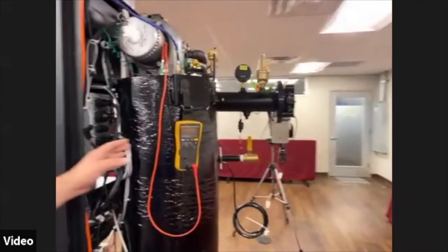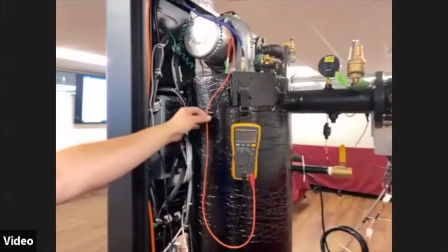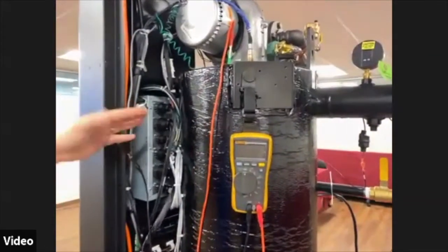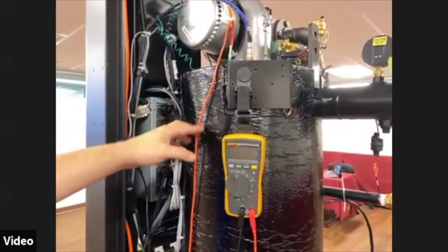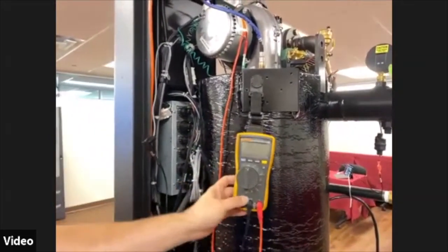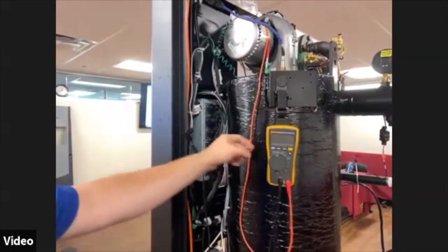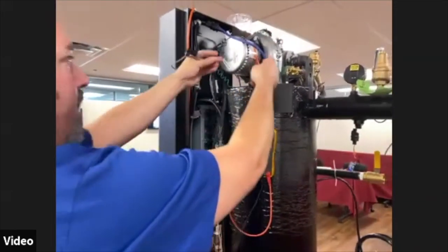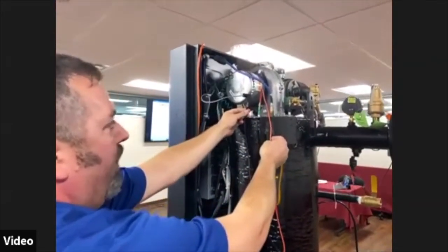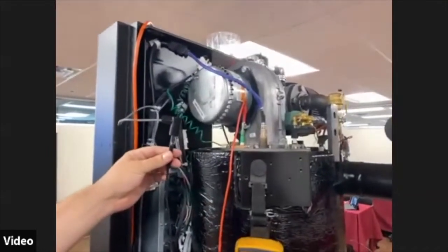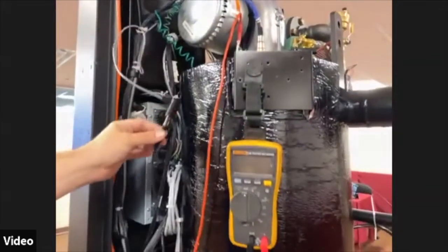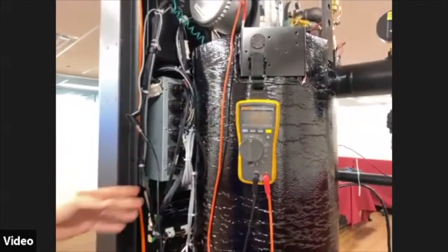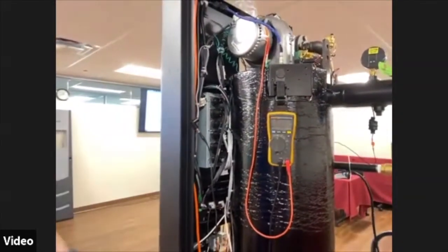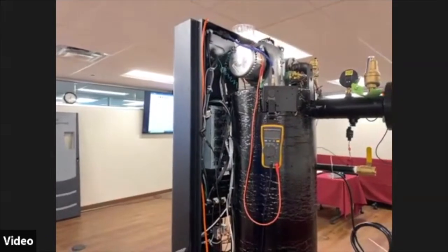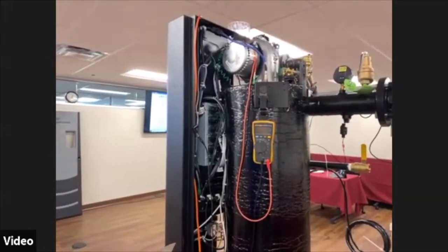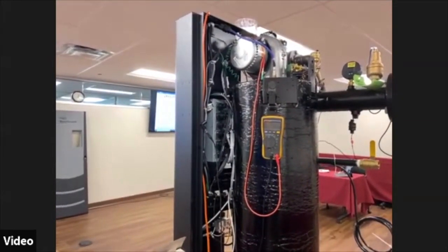The last thing to check out when you're doing your maintenance: if you're losing flame signal and you're not sure why, just to cover the basics, you can take a meter that measures microamps and wire it in line with your flame sensor. Take your flame sensor boot off, wire it in line, and once the boiler fires, you can read exactly what the boiler is seeing for microamps. And you can determine possibly if you have a bad flame sensor or a dirty flame sensor. That'll help you prolong the life of it and see exactly what's going on inside of that boiler.